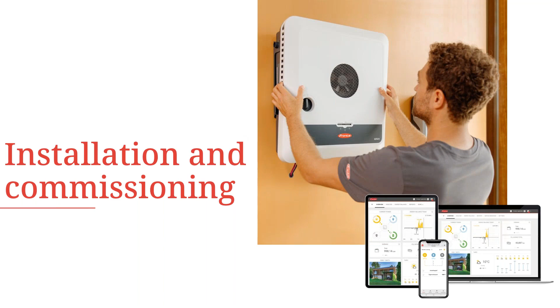When it comes to installation and commissioning of the Gen24 and Gen24 Plus inverters, you have a very easy commissioning procedure for both. First, the screws use a 180 degree quick release design, and we also have push-in spring-loaded clamps, so when connecting DC and AC power you don't require a screwdriver to secure the cables.